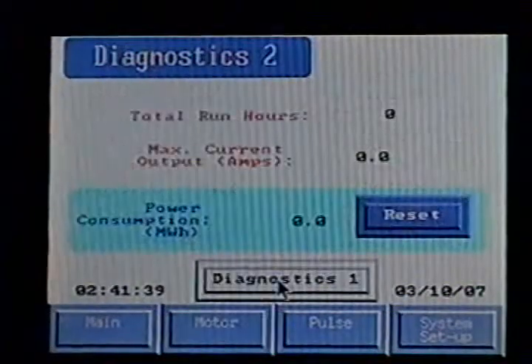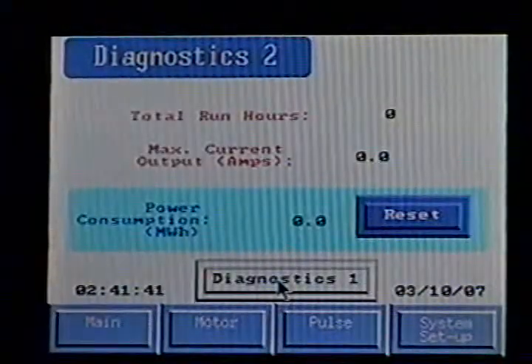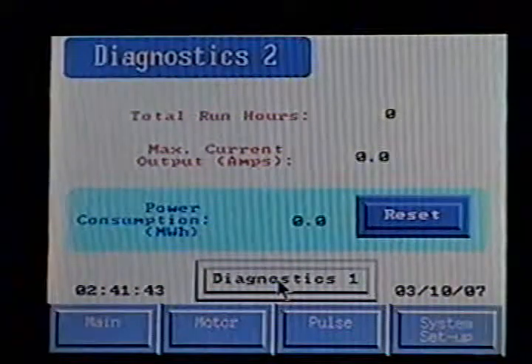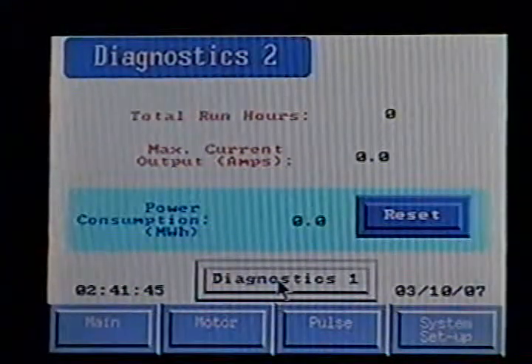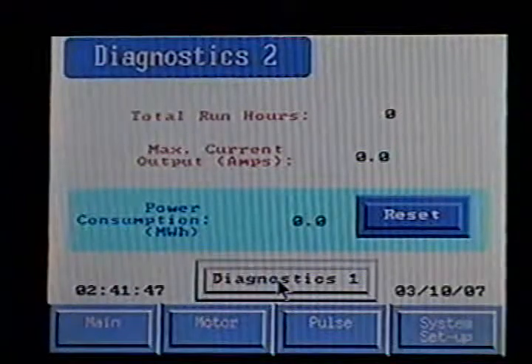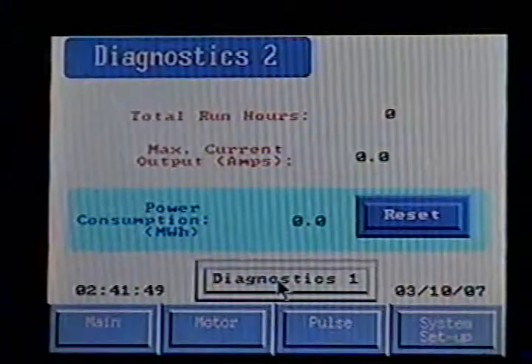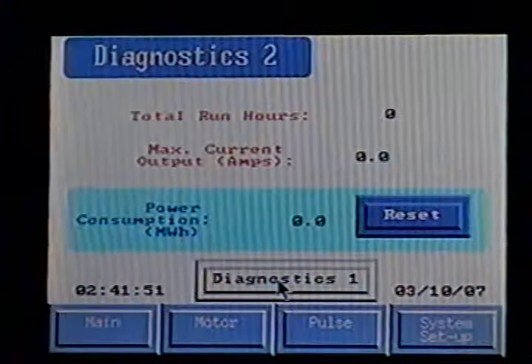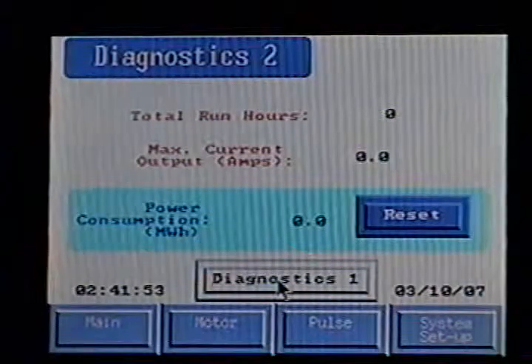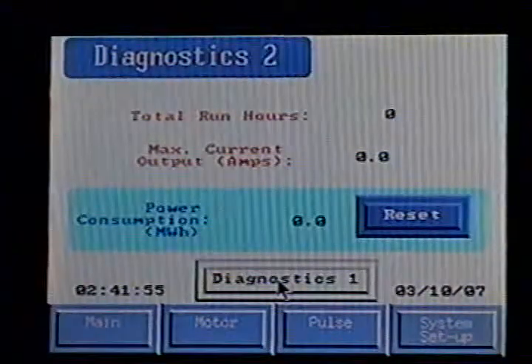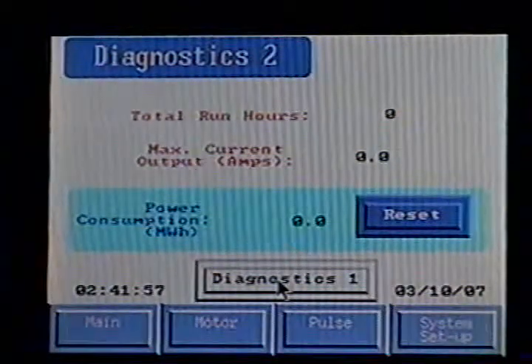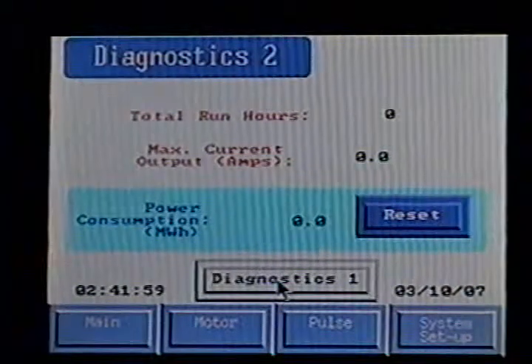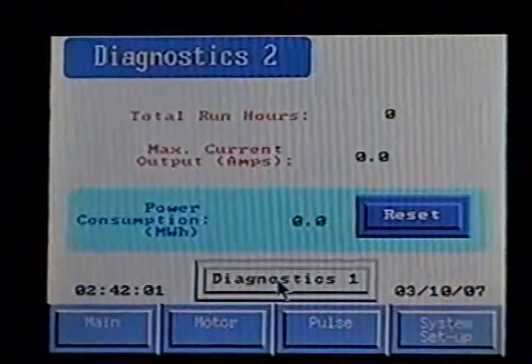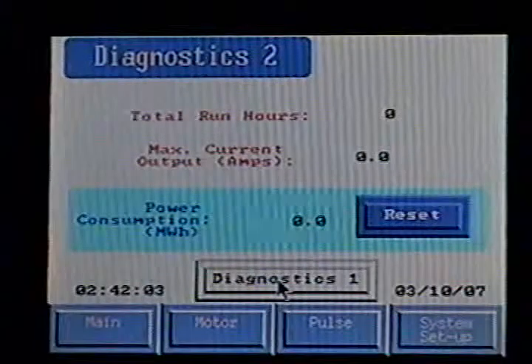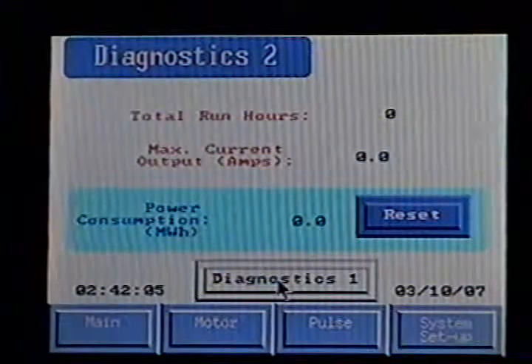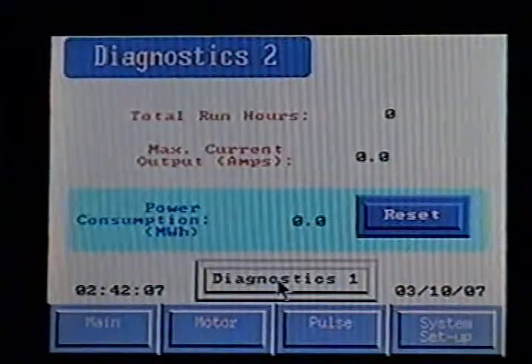There's a second page of diagnostics available: total run hours, max current amp draw. That would show if for some reason they have made some changes or had the wrong voltage or something, and they tried to hook up and run it at an amp draw above what we've preset here, it wouldn't be able to do it. And we can go in and look and see this is the max output of amps that they've ever gotten out of this collector.